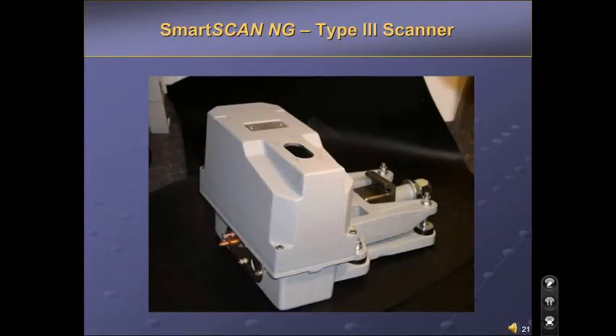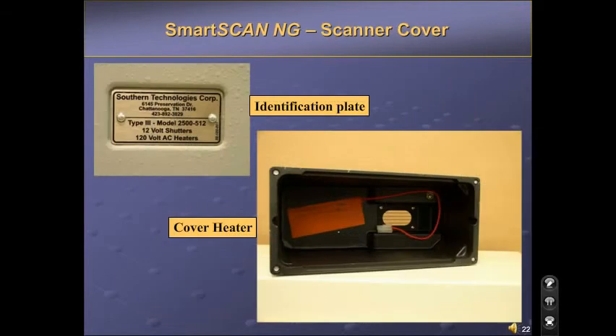This is the 2500-512 AC scanner. This scanner is made up of 3 systems: heaters, shutter solenoid, and Pyro block. This picture shows the scanner cover. Before plugging a scanner into a system, it would be a good idea to check the identification plate to make sure you are installing the correct type scanner.